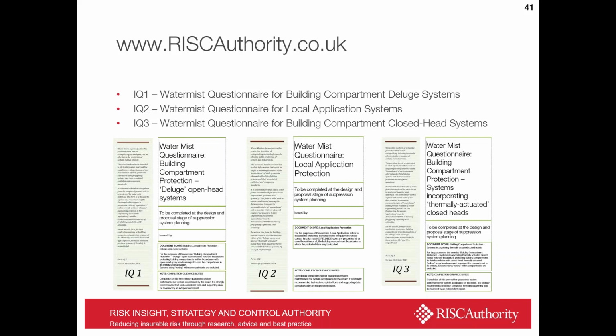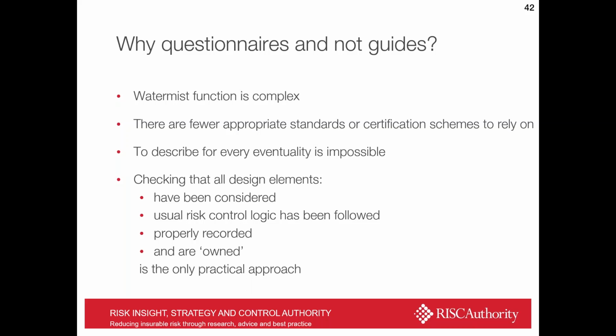IQ1 is the Watermist questionnaire for building compartment deluge systems. So that's the use of open head nozzles used to protect compartments in the same way that a gaseous system might be used. These are typically things that we see in some factory environments, but certainly greatly in the marine environment. IQ2, a Watermist questionnaire for local application systems, protecting deep fat fryers and cooking equipment, can be very effective there. And IQ3 is a special one. This is a Watermist questionnaire for building compartment systems which use closed head systems. These are things with bulbs in them. And there's some very good reasons, which I'll explain very shortly, as to why we think that's important.